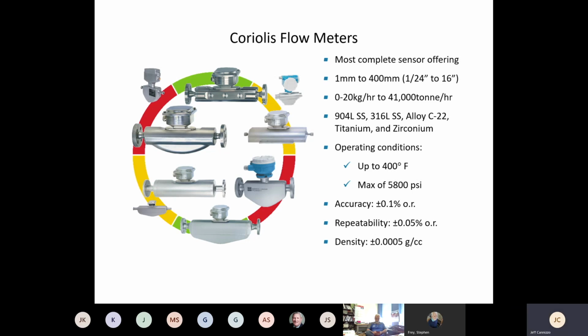A lot of people don't know this, but we make Coriolis meters as small as a 24th of an inch and as large as 16 inches. We make meters that go on filling machines that are small. You'll see them all over. So operating conditions, usually limited by temperature at the high end of about 400 degrees and about 5,800 PSIG.